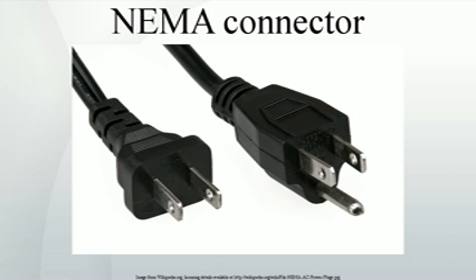The new receptacles are expected to reduce the number of electric shocks to children because inserting a normal, two-prong electrical plug applies pressure on both sides of the outlet to open an internal, spring-loaded shutter, but a foreign object fails to do so and therefore does not make contact with the live electrical contacts. However, the device can still be defeated by inserting two objects simultaneously. Despite its weaknesses, the tamper-resistant receptacle is superior to protective plastic outlet caps, which must be individually installed on each receptacle and are a choking hazard when removed, and to sliding covers that children easily learn to defeat.